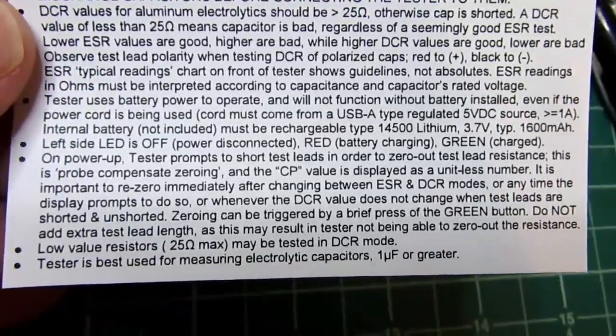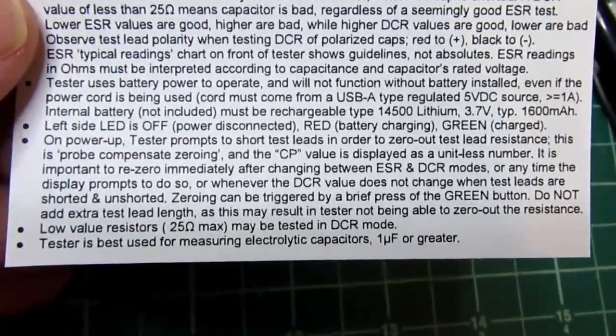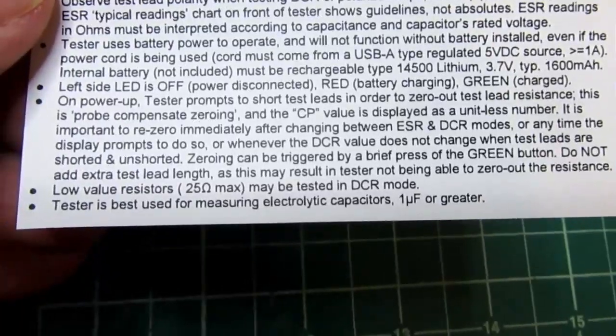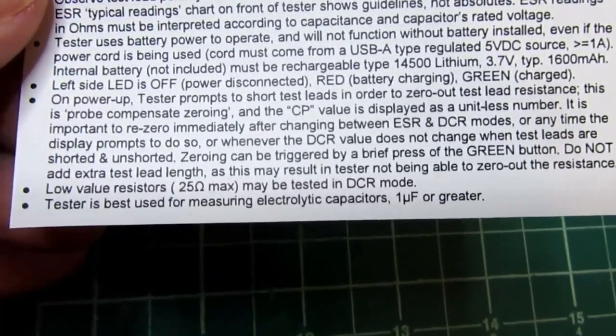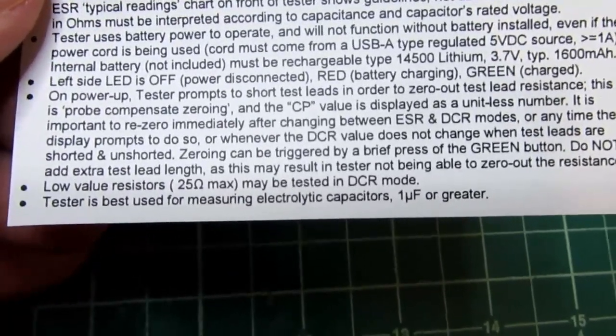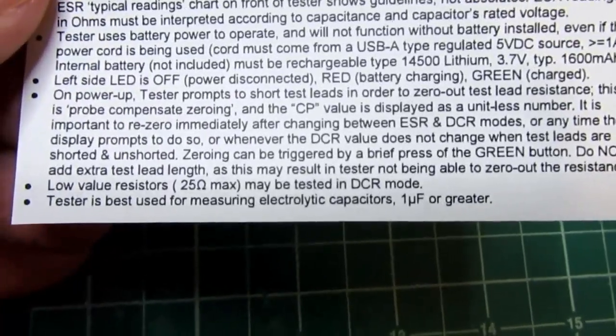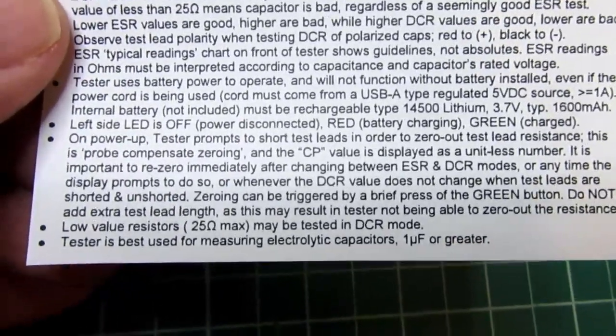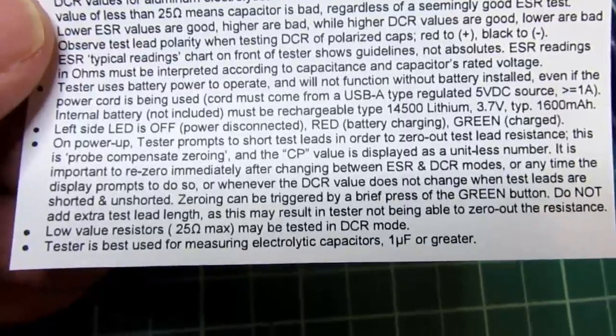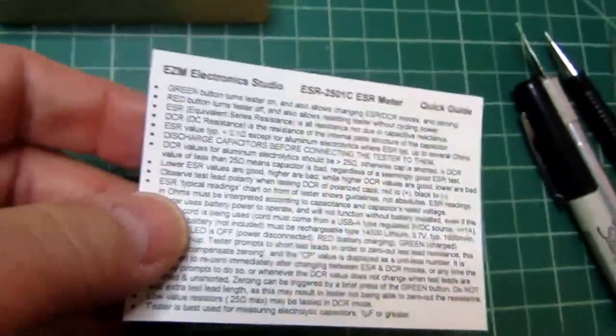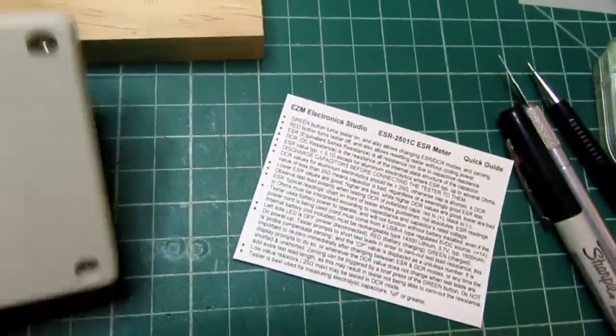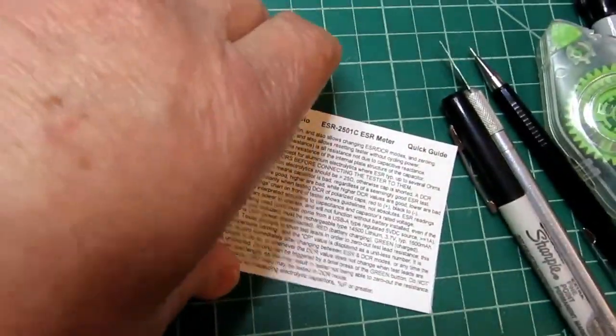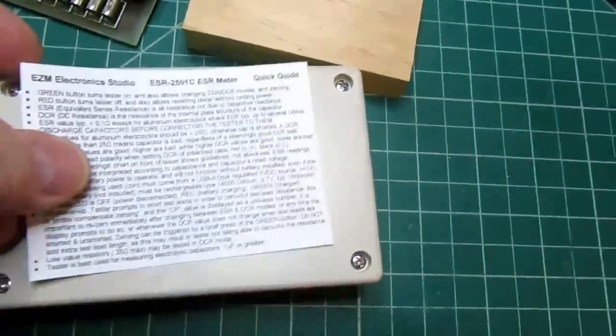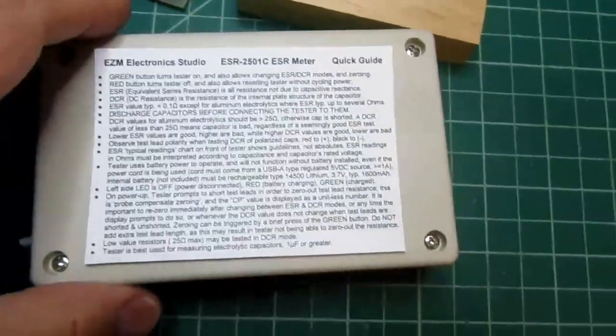Talking about zeroing again. It mentions that low-value resistors, less than 25 ohms maximum, may be tested in DCR mode. The tester is best used for measuring electrolytic capacitors of 1 microfarad or greater. And this is sized to be cut out and stuck on the back of the meter.